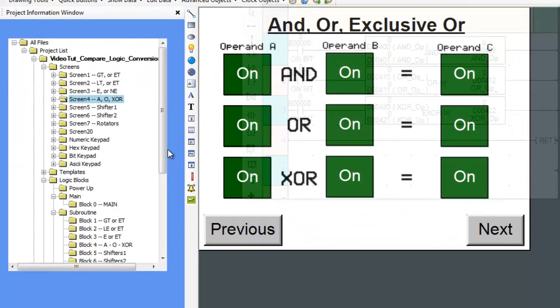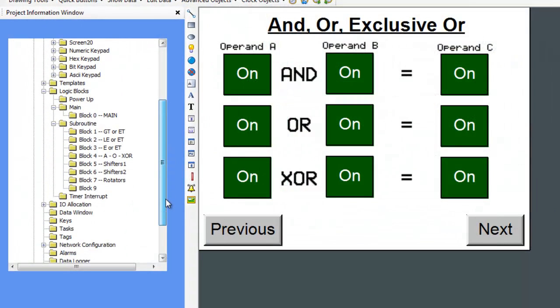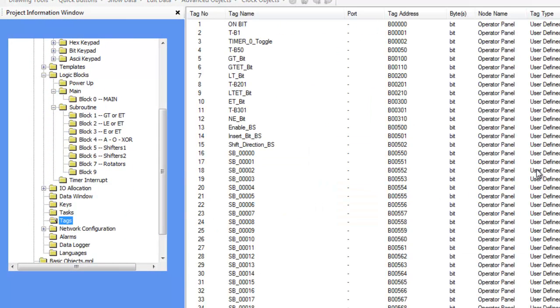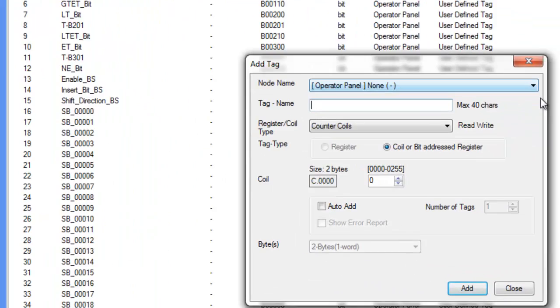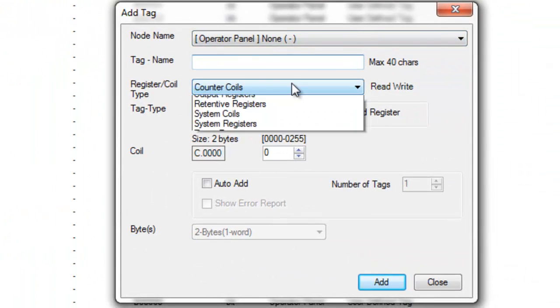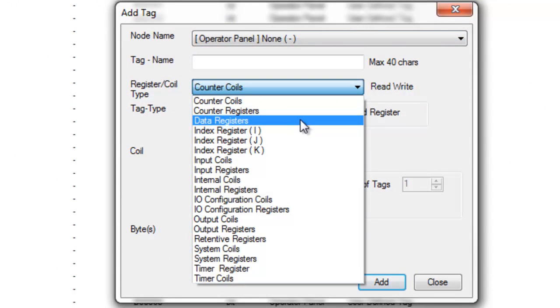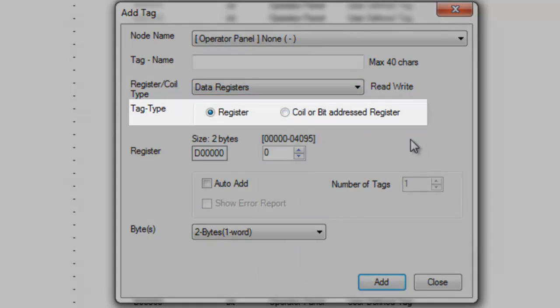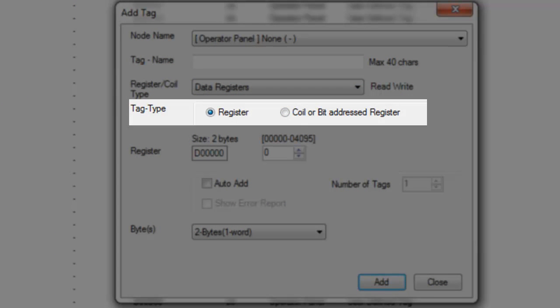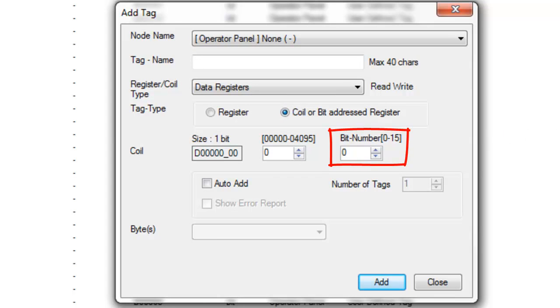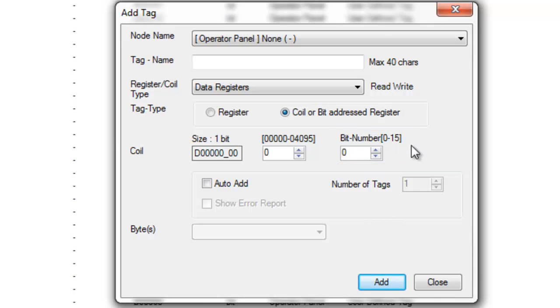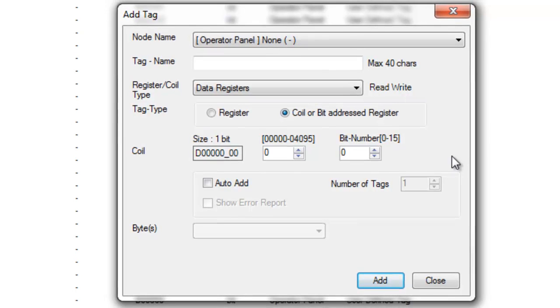Now let's explain how the registers in the ladder logic are linked with the coils that we assign to the buttons. When we create a new tag and choose a data register as a type, just like how it is on the screen, we have the option to choose the tag type. If we choose coil or bit address registers as a type, the bit number option becomes available to us. Notice that we can only choose from 0 to 15. That's because we are allowed to choose a particular data register with 2 bytes allocated to it, or a total of 16 bits. So what we are doing here is very simple.